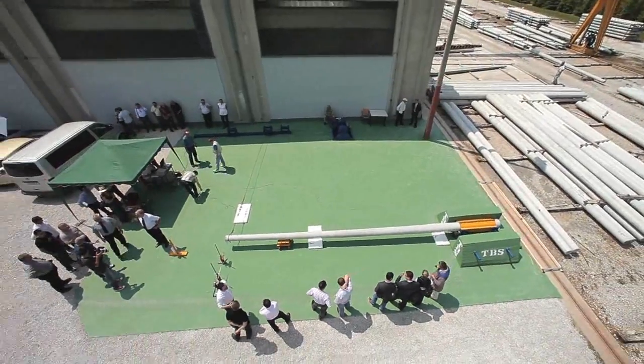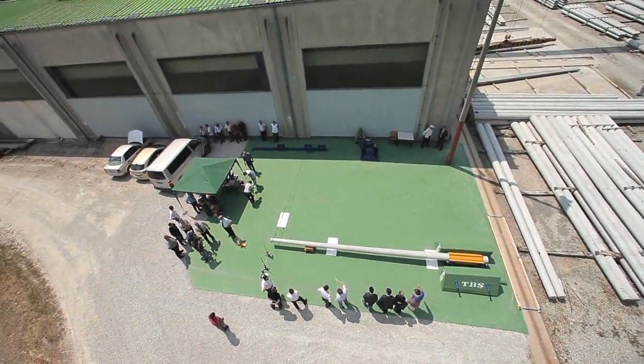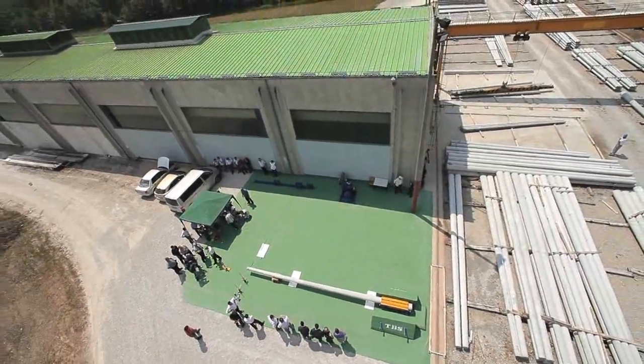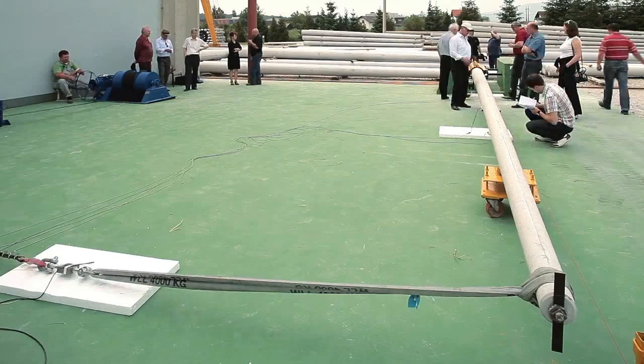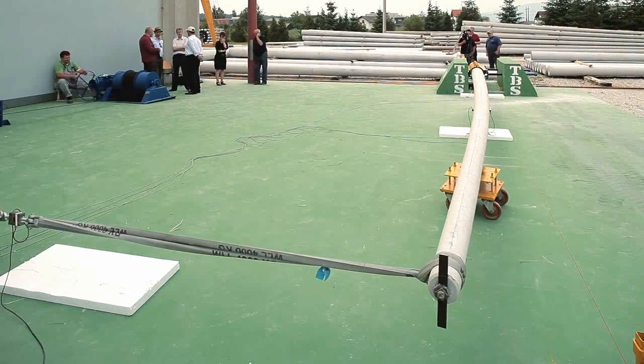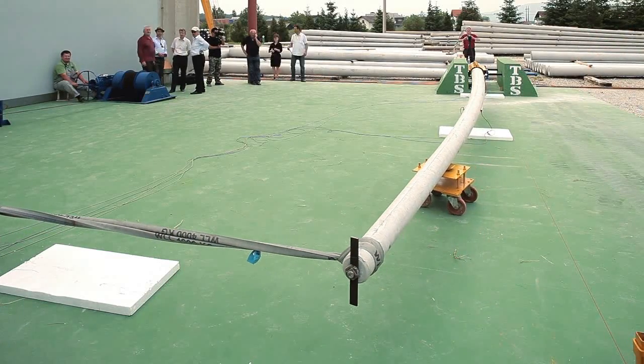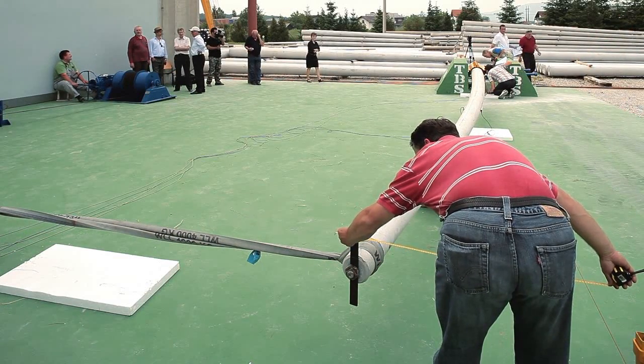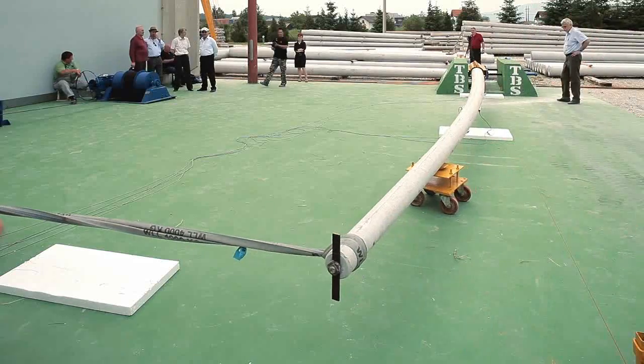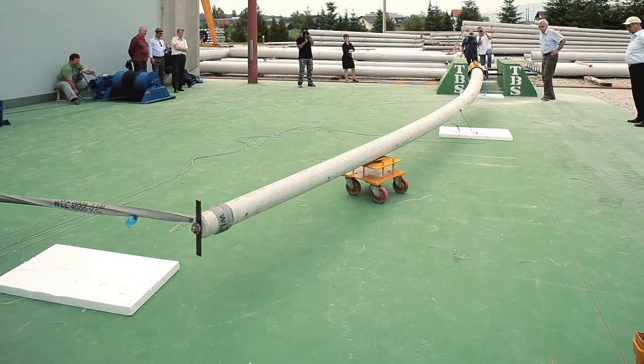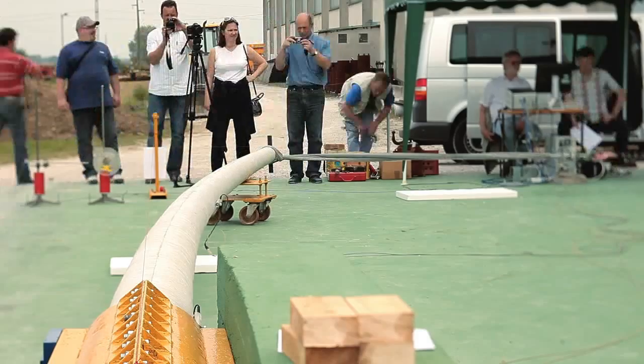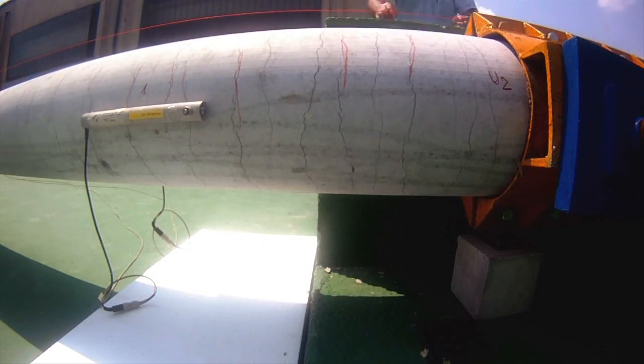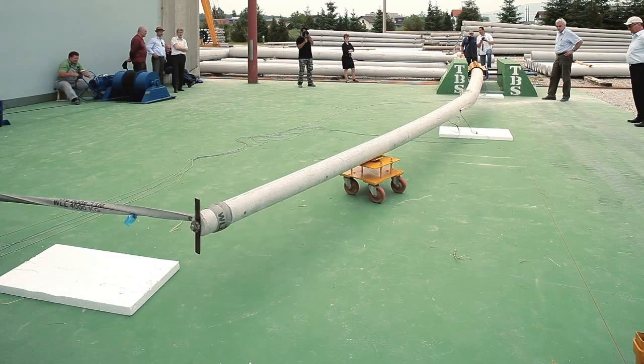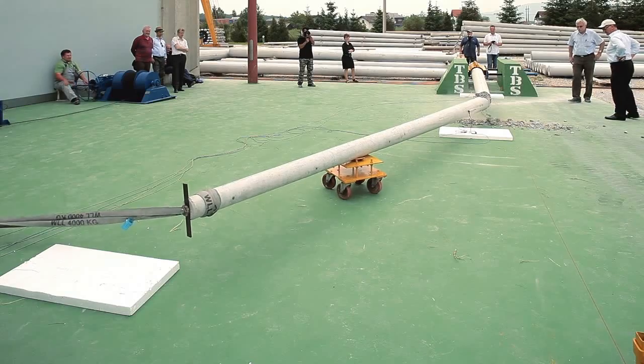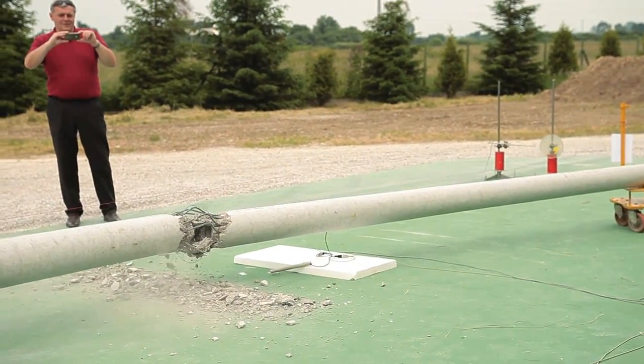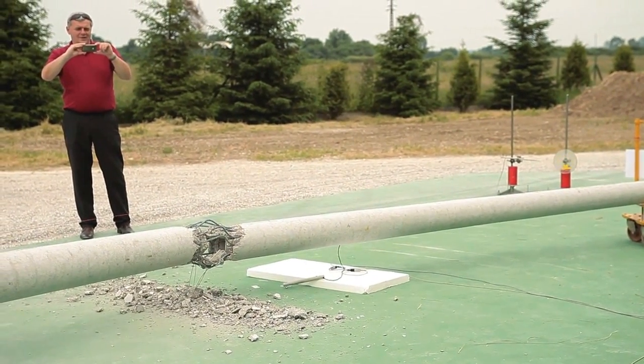The centrifuged reinforced concrete poles are tested up to the nominal force and fracture. With nominal force testing, poles are encumbered in two stages, first up to 1/2 of the nominal force and then up to the full nominal force. With fracture testing, we again have two stages, first up to the nominal force and then up to the fracture. According to Hrvatska Elektroprivreda branch standards, fracture safety coefficient is 1.8.